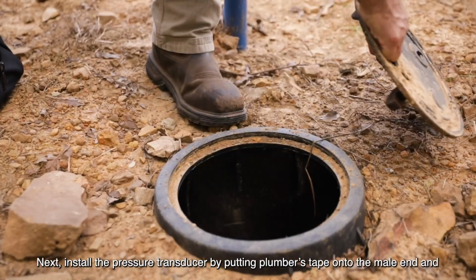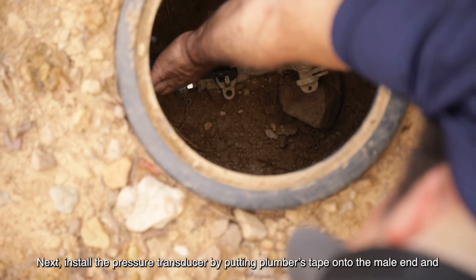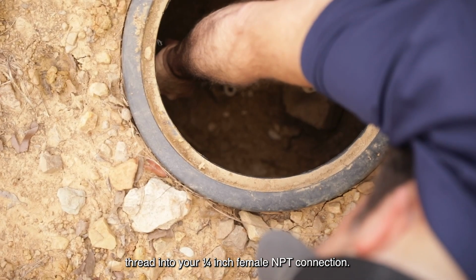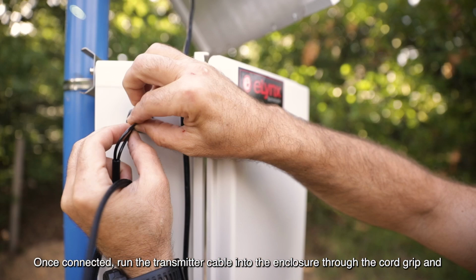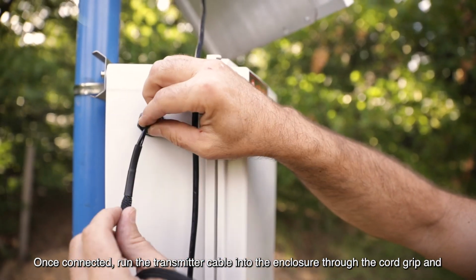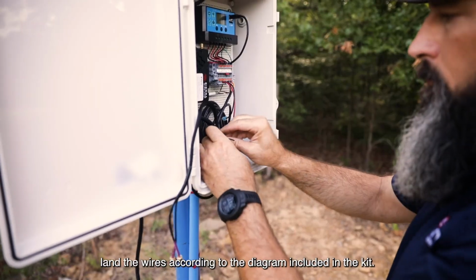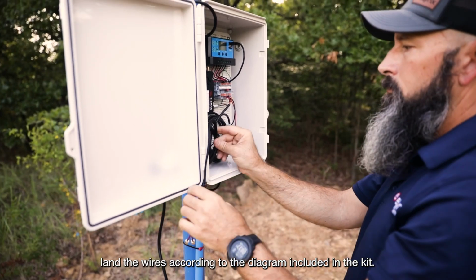Next, install the pressure transducer by putting plumber's tape onto the male end and thread into your 1/4-inch female NPT connection. Once connected, run the transmitter cable into the enclosure through the cord grip and land the wires according to the diagram included in the kit.